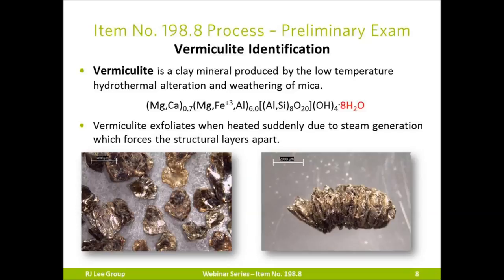Vermiculite is a clay mineral produced by low-temperature hydrothermal alteration and weathering of mica. Its formula illustrates that it has eight water molecules in its structure. When heated rapidly to 300°C, it exfoliates or expands due to steam generation, which forces the layers apart. Exfoliation can expand vermiculite up to 30 times its original thickness. Exfoliated vermiculite has very low density and provides excellent insulation, which is one of the reasons it is used in vermiculite spray-on fireproofing.